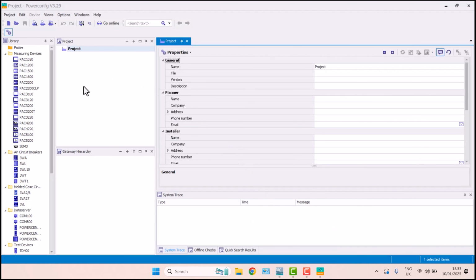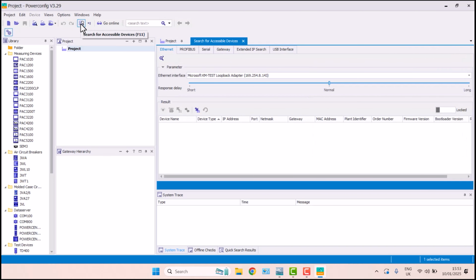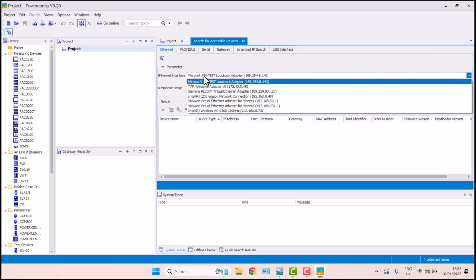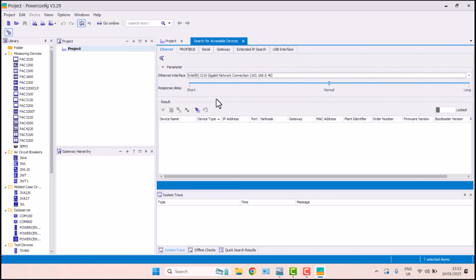So first thing we need to do is search for the device, so up here the tab, open that. Once this is opened, we need to go into the interface and change to whatever you've got it connected to. I've got the COM100 connected directly to the gigabit network on my PG. So select that and search for the device. So straight away it's come up with the COM100 here, and as you'll notice there's no IP address. This is how it comes out of the box. So first thing we need to do is add an IP address.